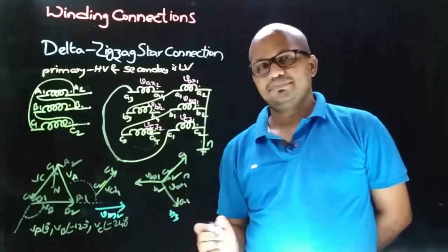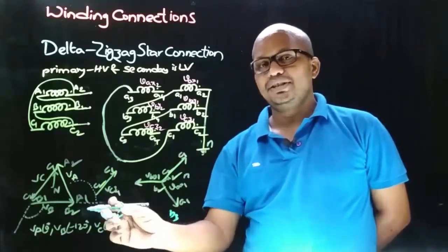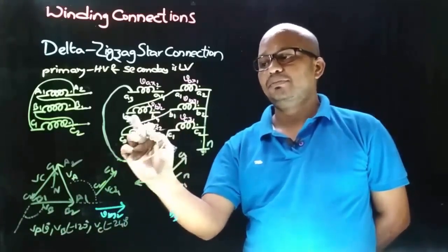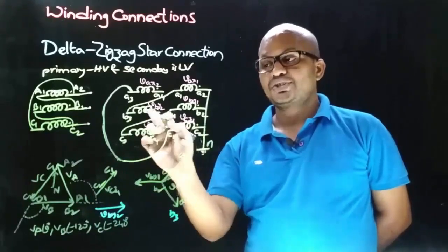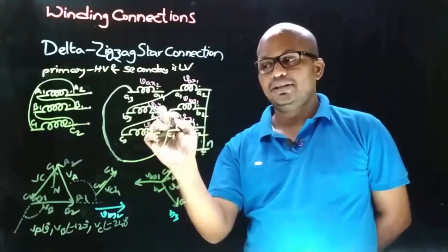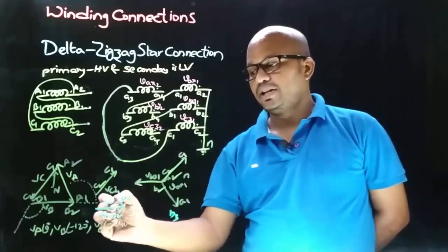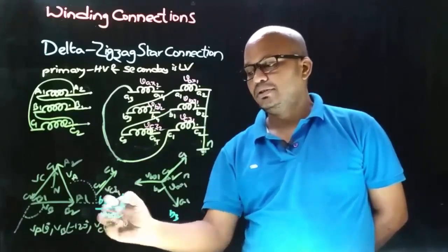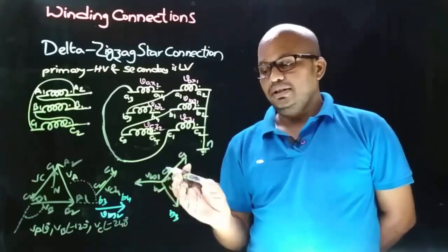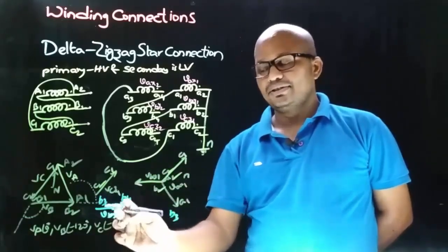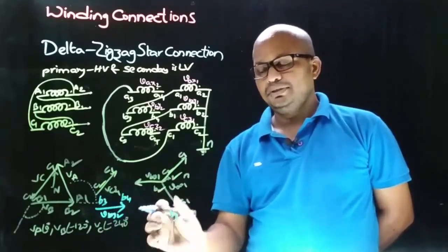So like this. And now we need to decide the terminals of the VB Y2 phasor. The terminals of the VB Y2 phasor are B3 and B4, and as the connection is taken from the dot end terminal, that is B4, therefore the arrow will point towards B4 and the other end will be B3. So now, in this phasor diagram, draw this VB Y2 phasor such that A1 will have B3.